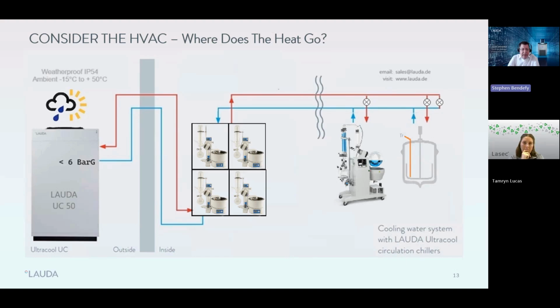And in that way, any heat generated by the chiller is automatically vented into the atmosphere outside rather than putting a heat load on the HVAC system. Because ultimately, the HVAC system would then generate more heat trying to remove that heat. So venting it straight into the air is a much better way of removing that heat from laboratory applications.